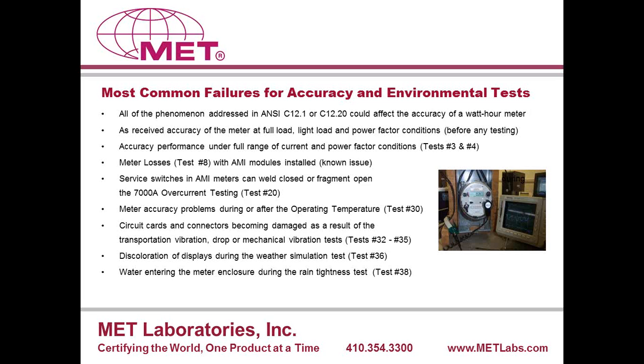It's not very long, so if you have, for example, if you're a utility that may have problems with yellowing or discoloring of the meters or domes, you may want to run a program that goes a bit longer than that. And on occasion, this has not been too much of an issue lately, but rain tightness tests, we may see some intrusion of water within the meter itself.